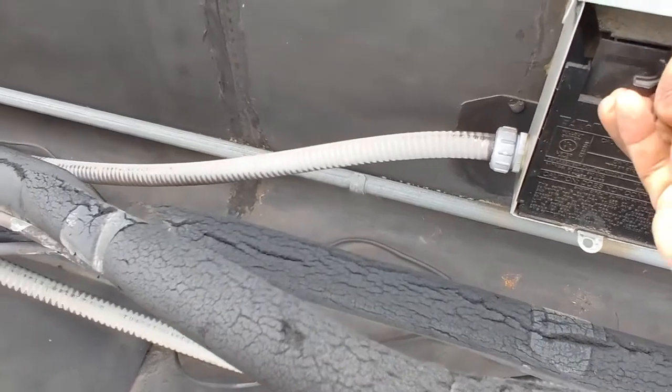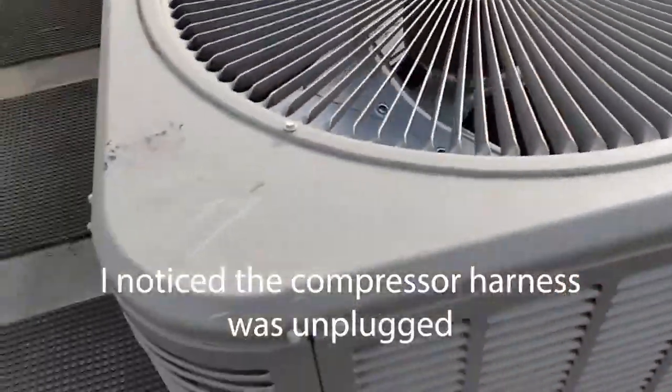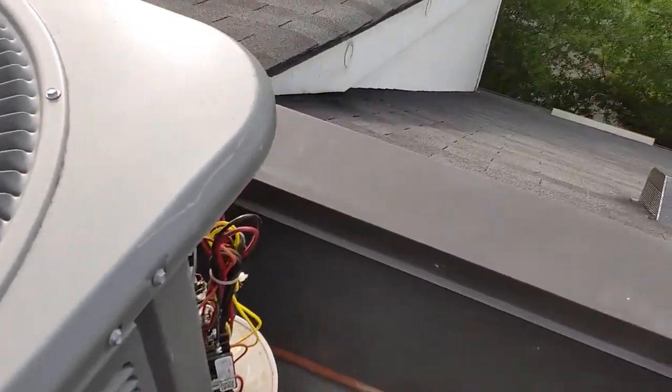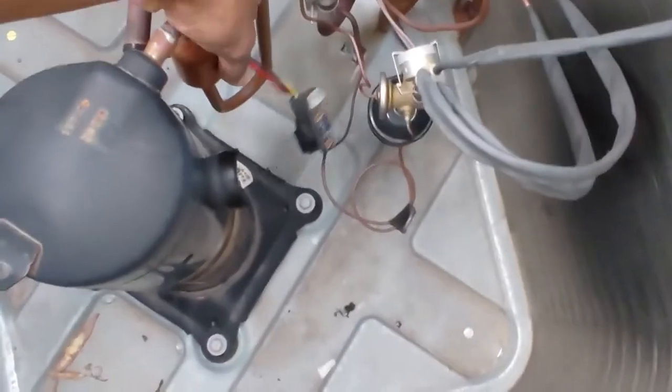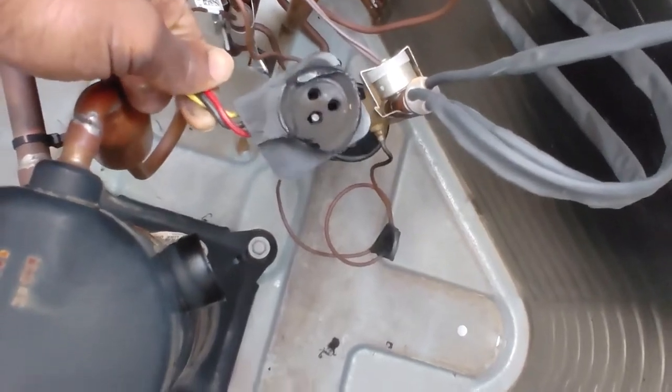Hermetic, common, fan — let's go ahead and plug it back in and see what we got. Looks to me it just... blew out. Move that terminal — blew the terminal out.